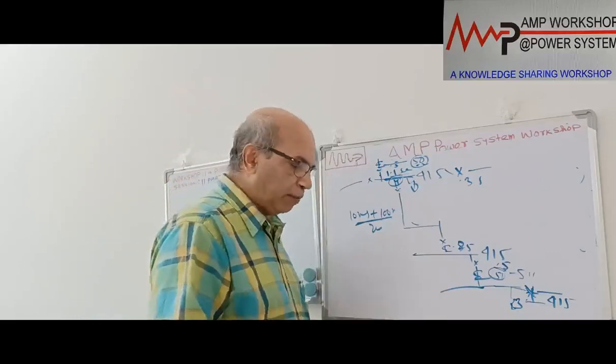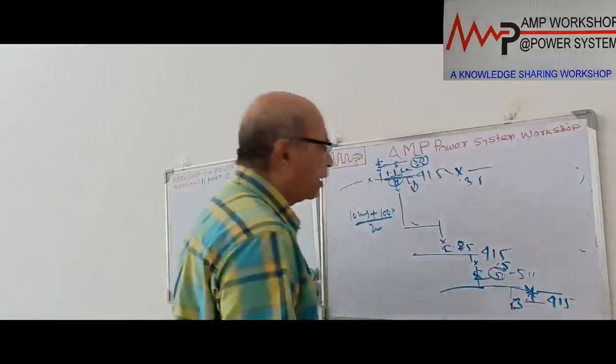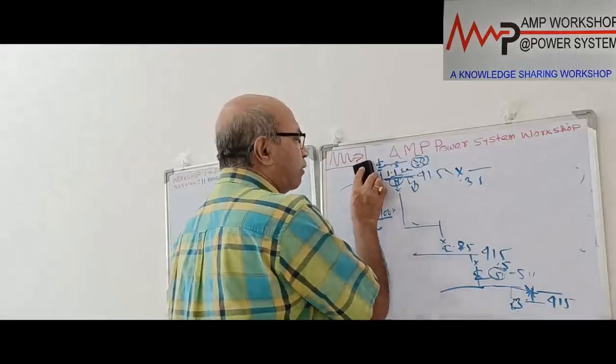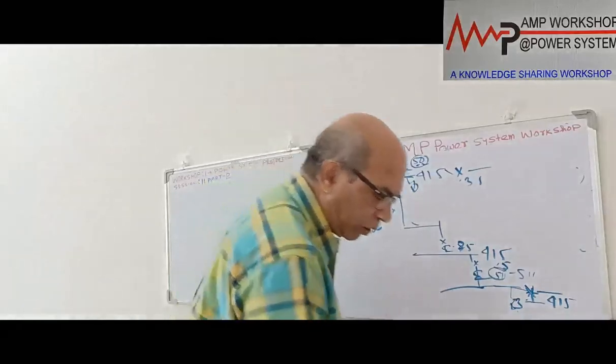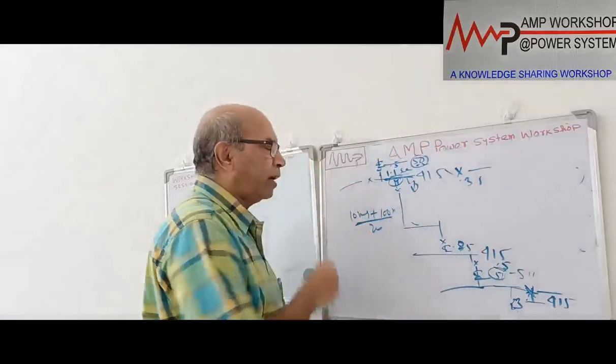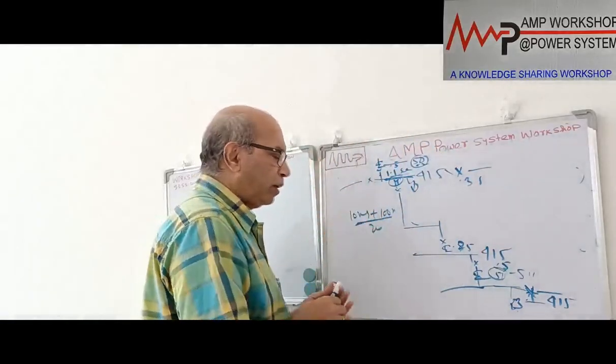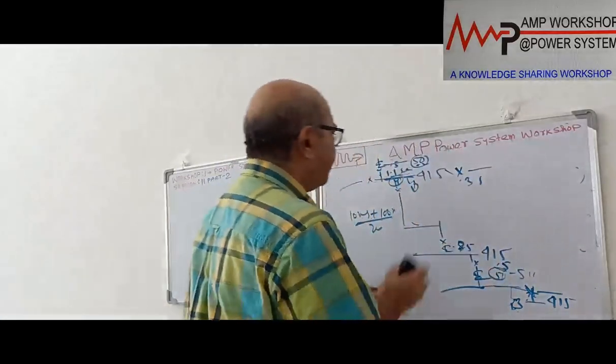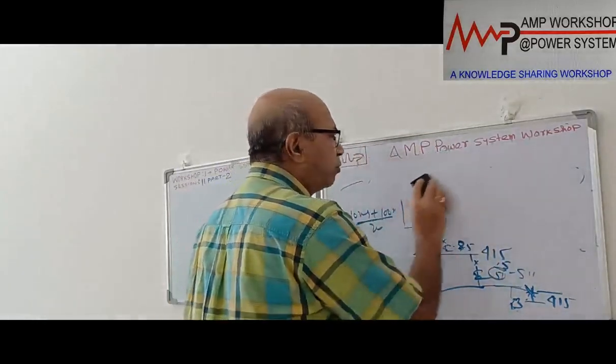So this is about the protection for the low voltage switchgear for the bus bar fault with the bus section. But one of the things over here: when the low voltage switchgear bus bar protection operated, this overcurrent relay operated. You know, all the low voltage schemes have an auto changeover scheme. The auto changeover scheme should be blocked.